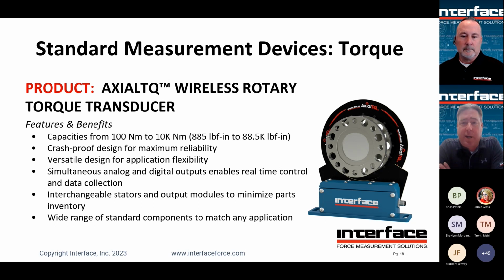What happens if you break an axle shaft and perhaps the output shafts start whipping around? This is designed so that you have essentially no contact between the rotor and stator, and it will tolerate a greater degree of misalignment than a standard transducer would. So that's what we call a crash-proof design. These are available in capacities from 100 newton meters up to 10 kilonewton meters.